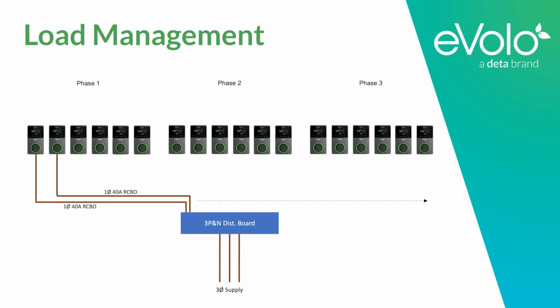When charge points are installed in areas that are powered by a landlord's electrical supply, the EV load management can be managed through the app. In situations where these charge points are powered from a dedicated distribution board for EV charge points only and are rated at 7.4 kilowatts on a single-phase radial circuit, the load on each phase can be managed to ensure it is not overloaded to dangerous levels.